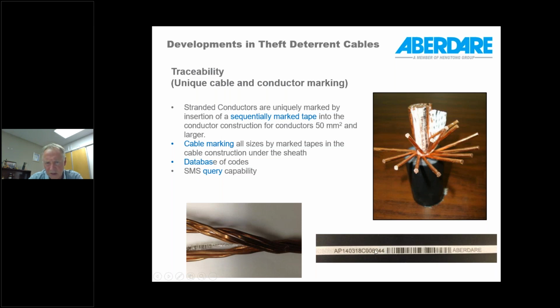It's a white colored tape. It's about 4 mm wide, and it provides traceability in terms of the manufacturer and in terms of the tape supplier, as well as a code that changes every meter along the distance. Sorry, every 100 millimeters along the length of the cable. So the idea is that if you know the number at one end of the cable as well as at the other end of the cable, then you know all the numbers in between, because this is a sequential code that's applied.